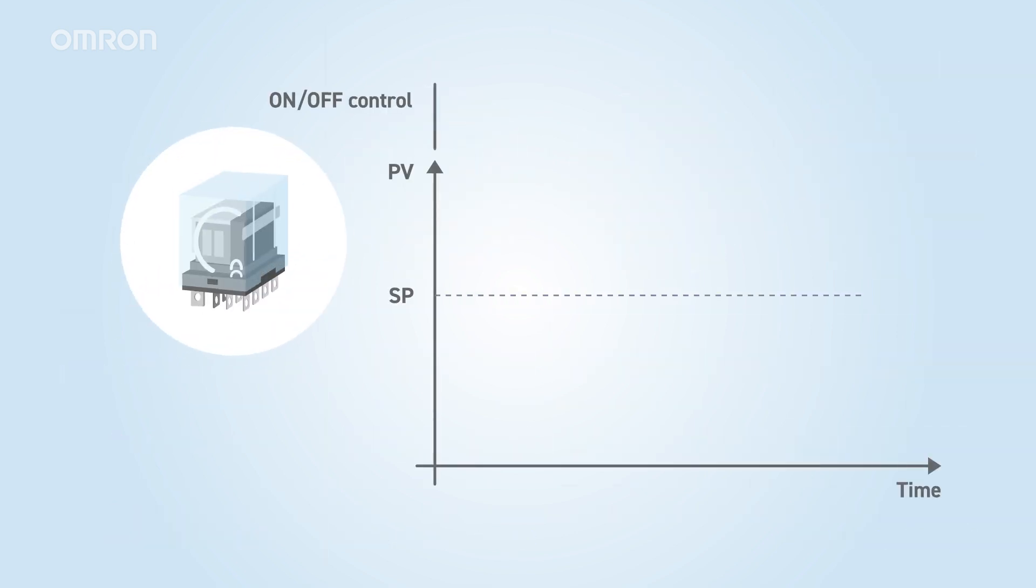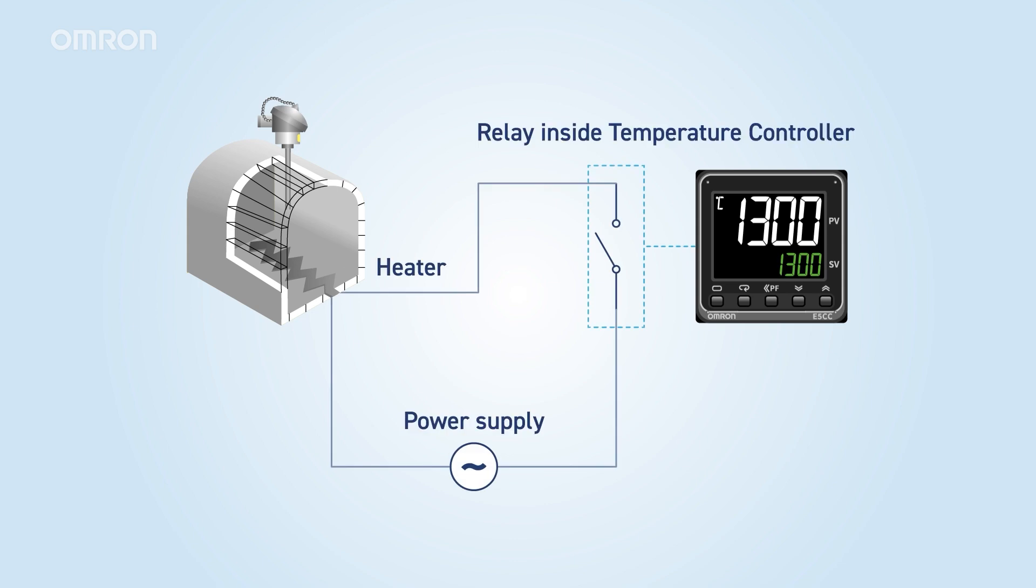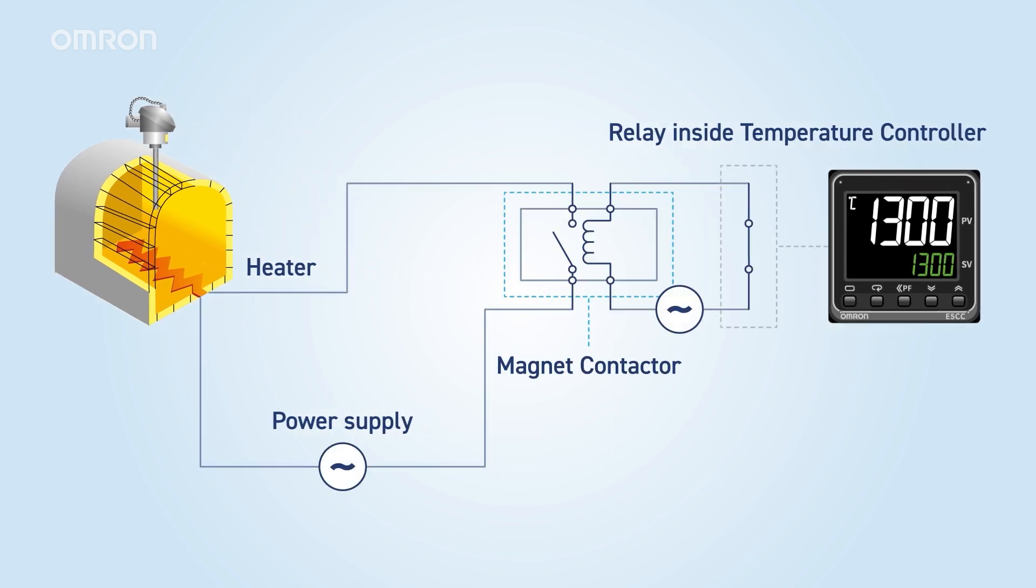Relays open and close contacts using an electromagnet. Due to the limited lifespan of the contacts based on the number of open-closed cycles, they are not suitable for equipment that require frequent and rapid switching. They are commonly used for on and off control. Additionally, relays generate less heat, allowing for smaller output device sizes. Relays are built into temperature controllers with relay output types, enabling direct on-off control of heaters. If the heater current exceeds the relay's allowable current, the heater is turned on and off via the magnetic contactor.